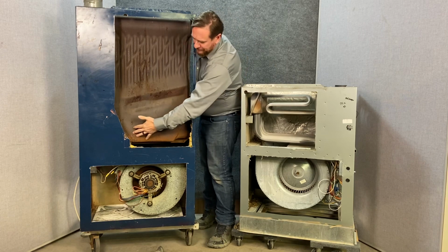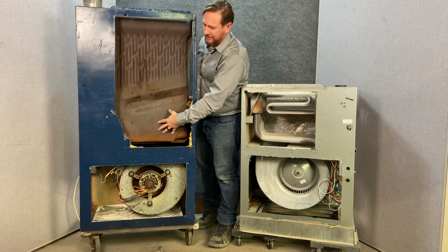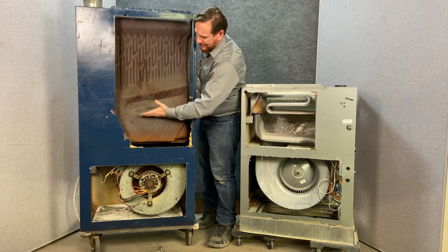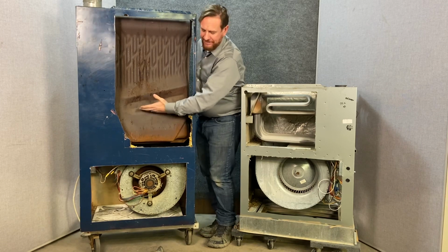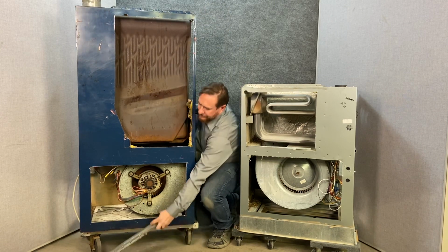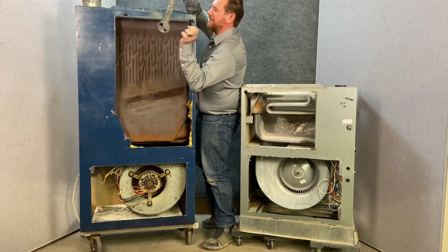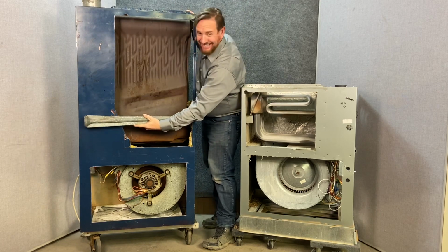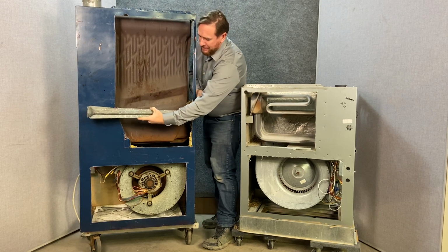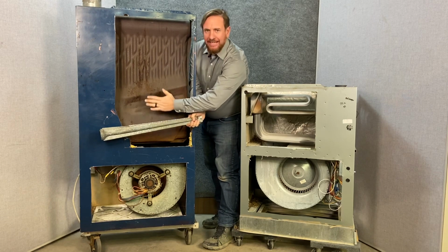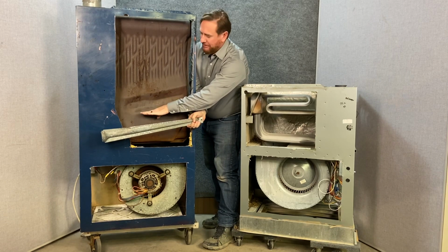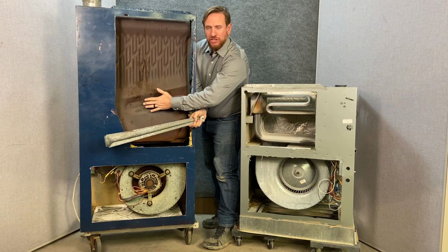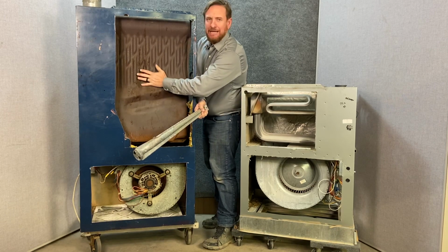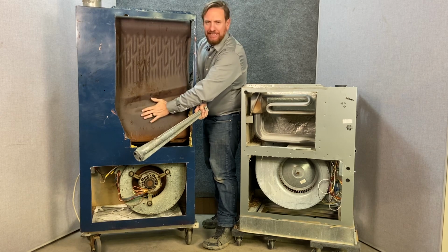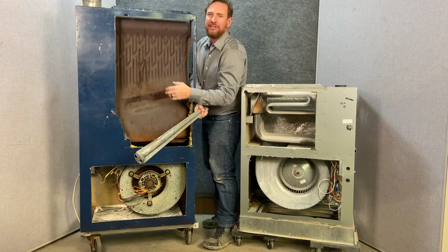The very bottom side of this one is where the burners are going to be, and the flame's going to be burning up about no more than about this high right here. These are the burners that we would have. They would be sitting inside of this heat exchanger, burning up. Once the flame stopped about here or so, the gases are still going to be extremely hot. Those gases are heating up the metal from the inside, and this is exchanging the heat from the flames and the hot gases to the air on the opposite side.